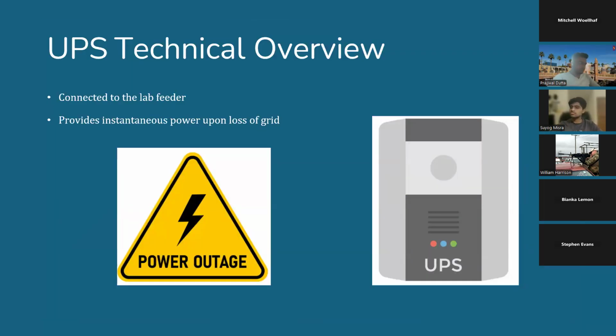The UPS in our microgrid system is a critical component designed for simplicity and reliability. It is directly connected to the feeder powering the lab, and in the event of a power grid outage, it seamlessly provides 5 minutes of power supply. This ensures that our prioritized load continues to operate without interruption. The UPS achieves this by storing energy in a battery bank as DC voltage. When needed, it efficiently converts the stored DC voltage into AC voltage, delivering a stable power supply to keep essential operations running.